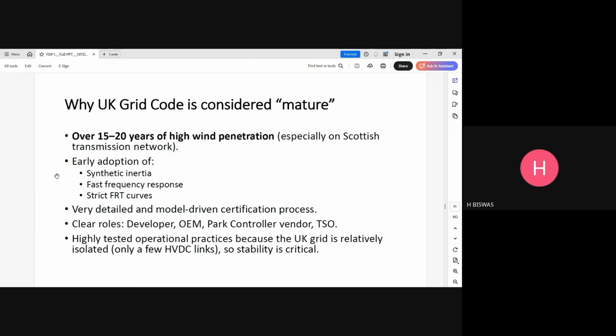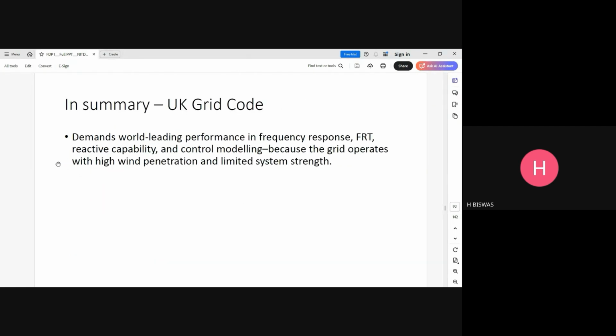Now, one of the things: the UK grid is considered to be mature, in quotes. They have offshore wind, with over 20 years of high wind penetration, particularly Scottish and Southern Energy and the Scottish Transmission Network. They were among the first early adopters of synthetic inertia, fast frequency response, strict FRT curves, and a very detailed, model-driven certification process. They have clear roles: developer, OEM, Park Controller vendor, TSO, and highly tested operational practices, because the UK grid is a little bit isolated. If you discount, of course, that it is connected by an HVDC link with France and Belgium, it is only a few HVDC links. But again, the stability is very critical. In summary, it demands world-leading performance in frequency response, FRT, reactive capability, and control modeling, because the grid operates with high wind penetration and limited system strength.